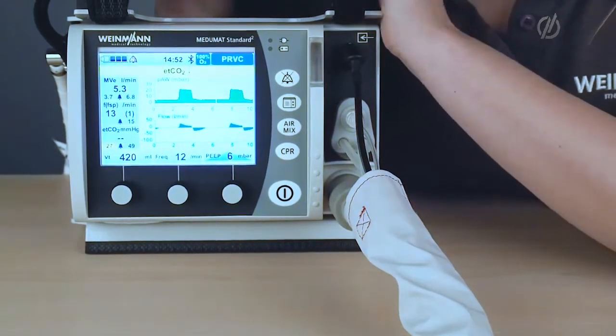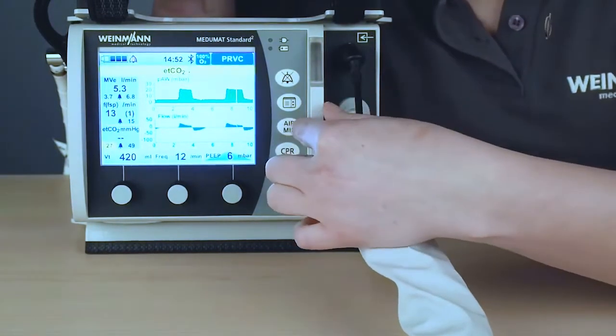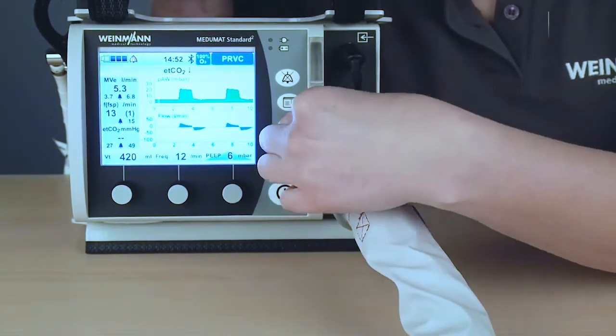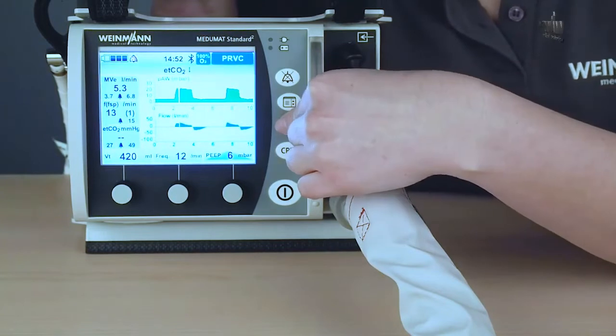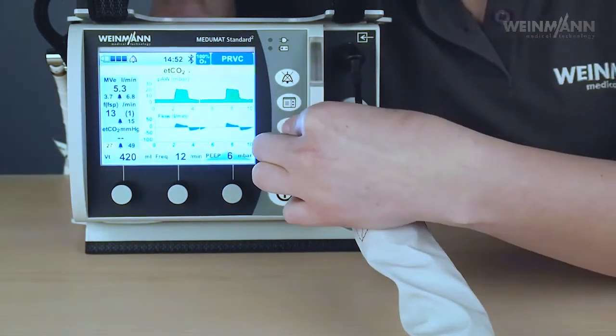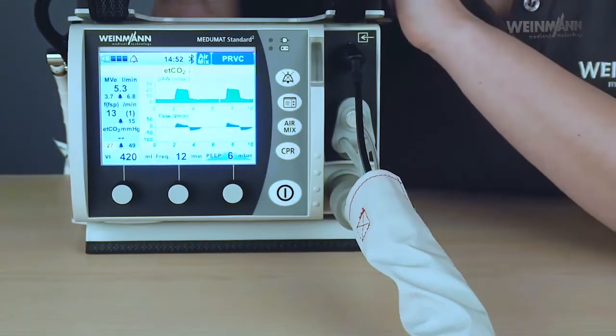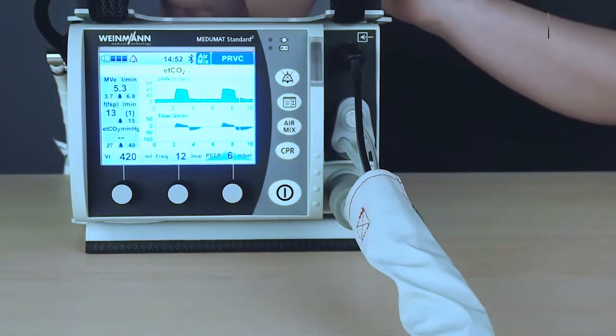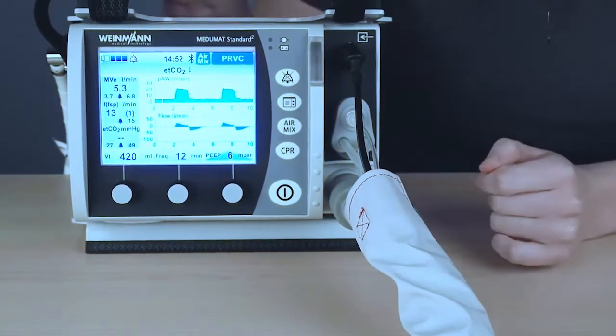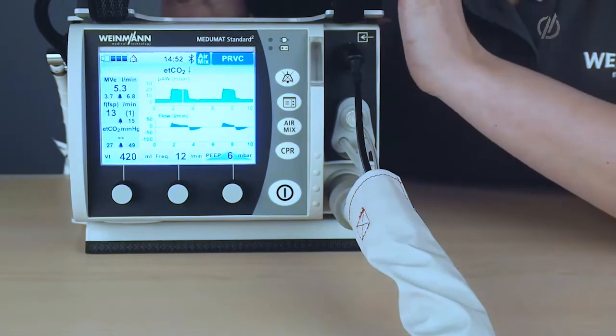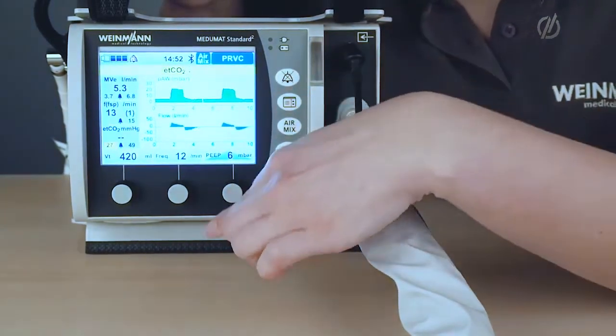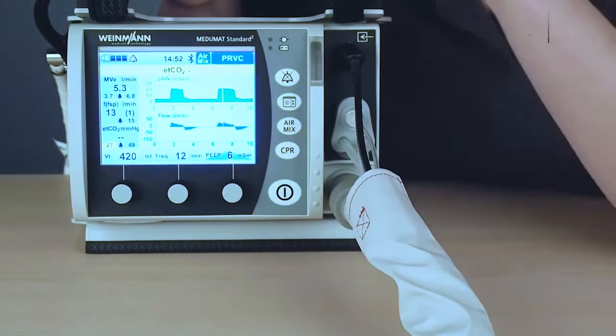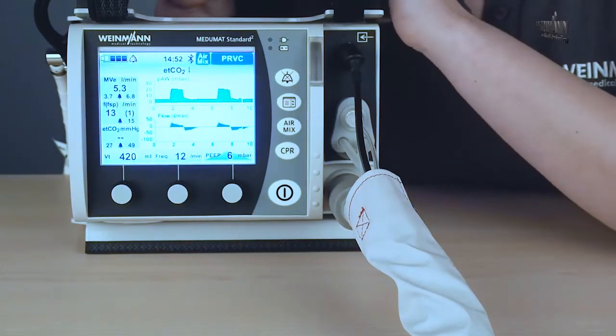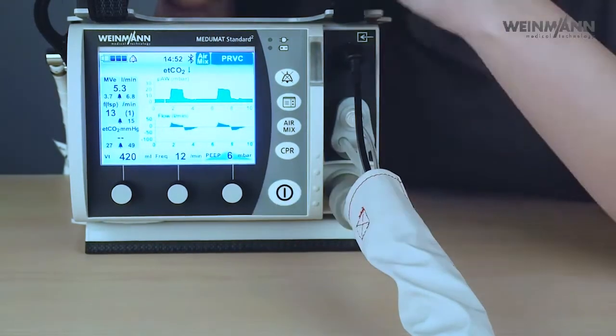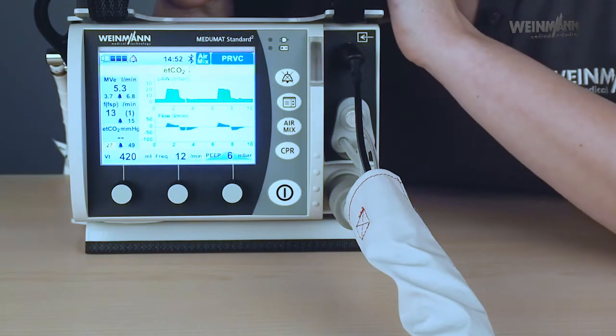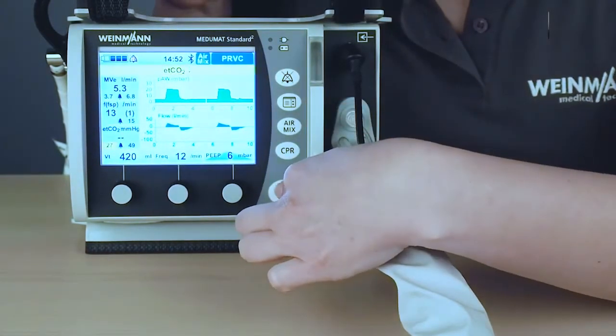One thing that I would like to show you also is the air mix button. So the device has the possibility to choose between 100% O2 and air mix. So if I press here, you see it here in the display, the device will suck in air through the hygienic filter and mix it with the oxygen from the bottle. So this was it, and I will show you right now this special CPR mode in a different setting.